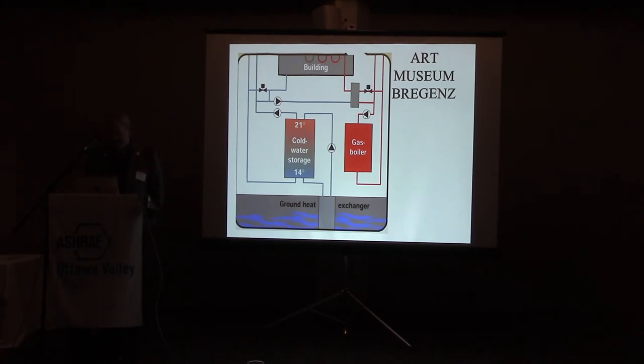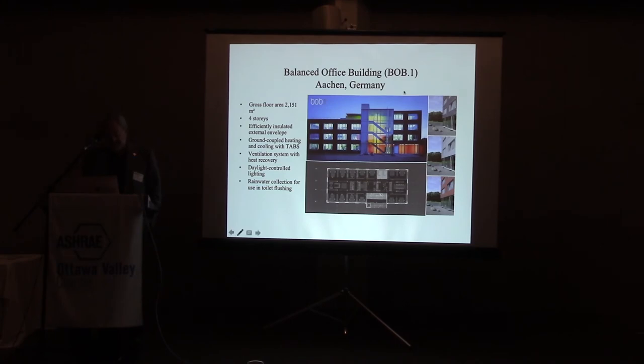Nowadays we often see in Europe that small offices use a TABS system where piping is integrated in the concrete slab, giving storage possibility to lower the peak and transfer some of the heat from daytime to nighttime. The buildings are normally well constructed in the facades. You have to spend a little more time on the design to keep down the loads. That's important because this system has limitations in how much it can move. So a well-designed building is needed. Also, when you have a lot of big windows and a lot of sunshine, you have to look at solar shading.